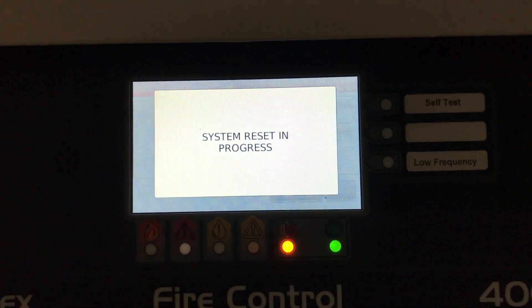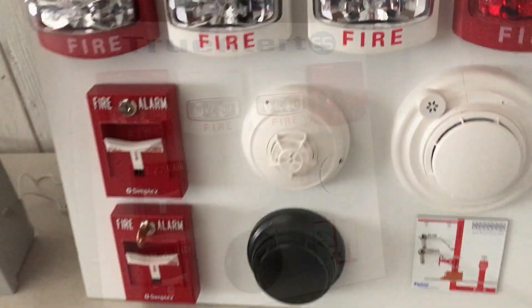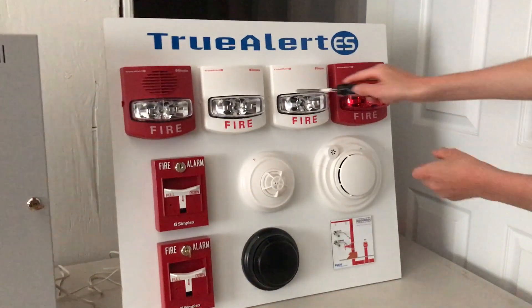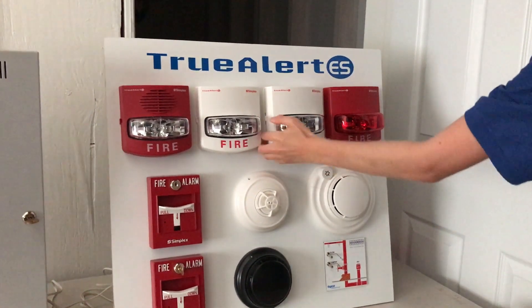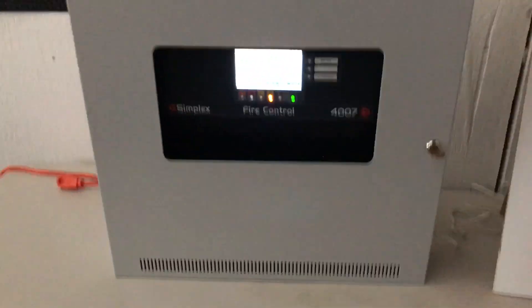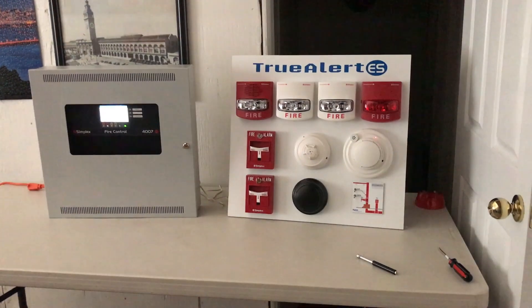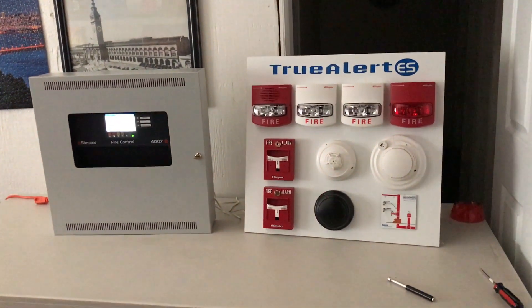The last thing I'm going to show is the supervision feature. If I were to take the device off — like this — and someone were to remove it, as you can see we took the alarm off and there are the wires. Going to our panel, it's giving a trouble signal. We go ahead and acknowledge that trouble by touching acknowledge. Thank you for watching — I hope you enjoyed the demo for the 4007ES.